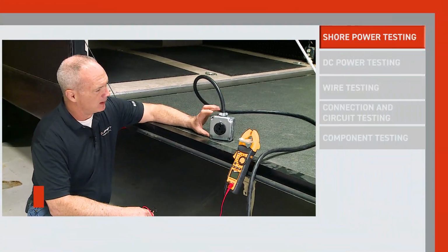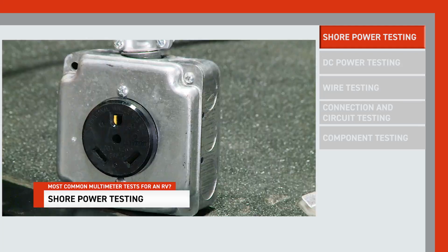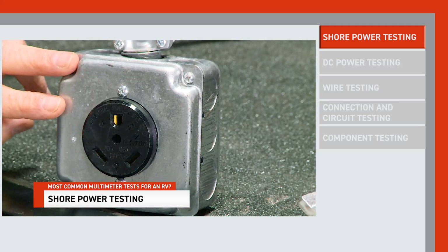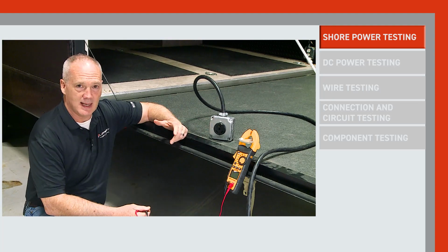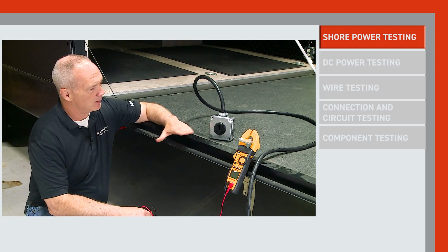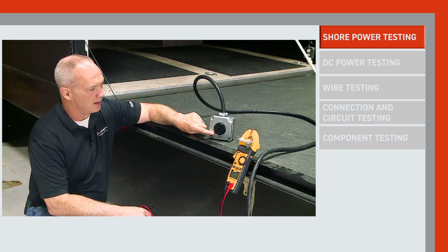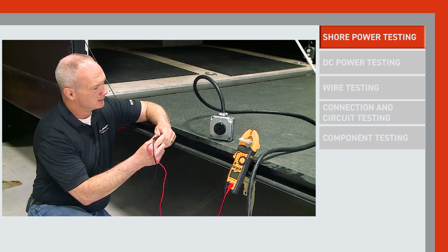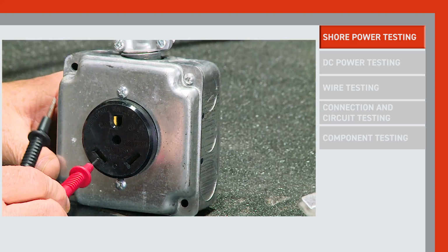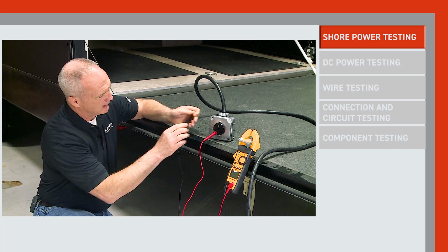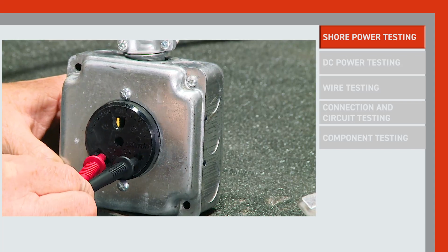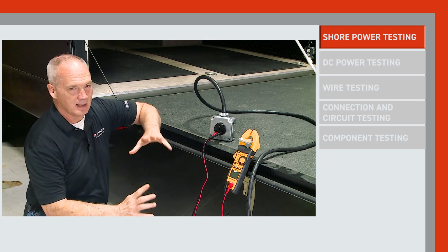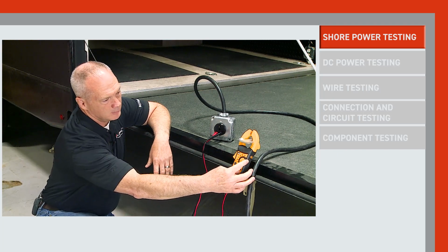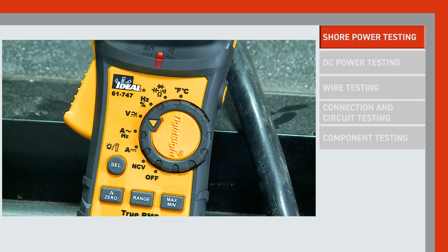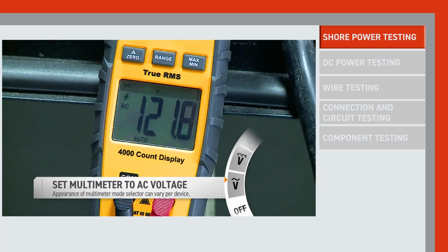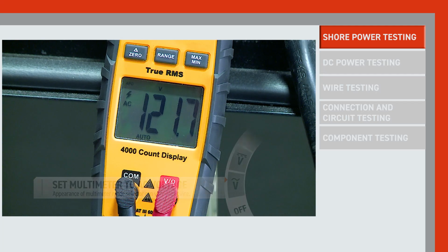Here we have a replica of what a shore power terminal looks like. This is a 30 amp, 120 volt receptacle, just like you'd find at a campsite. So I'm going to make this simple and check one area for that 120 volts AC. I'll take the positive lead and put it in this left terminal and the negative lead in the right lower terminal. Now that those are making contact, I'll take my selector dial and put it on volts, make sure it's on AC, and you'll see 121 volts AC.